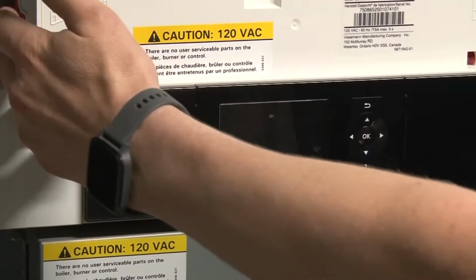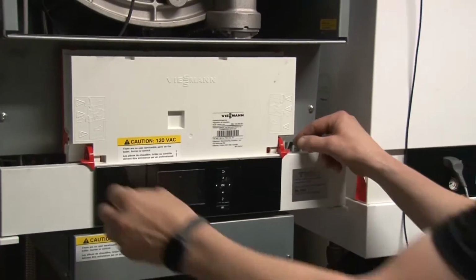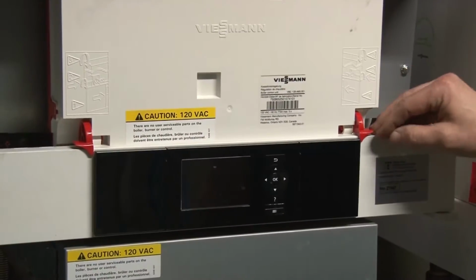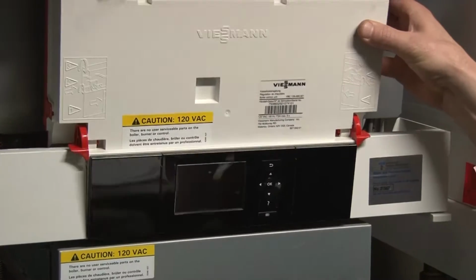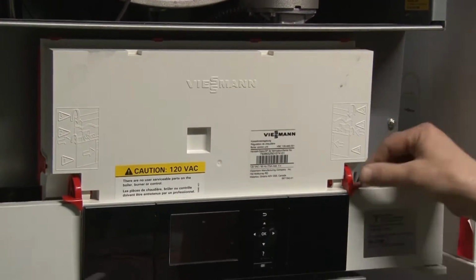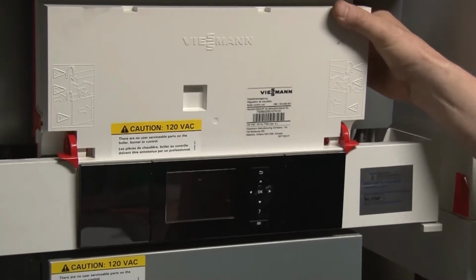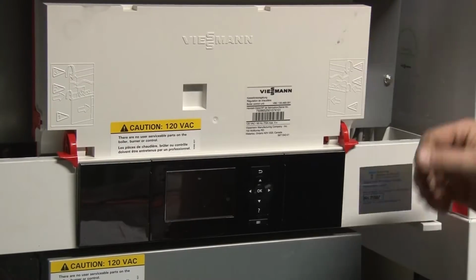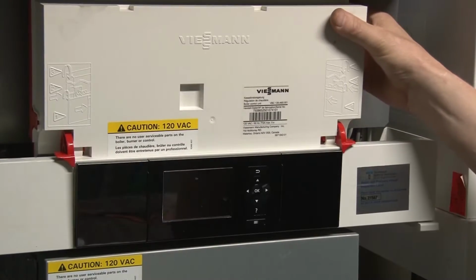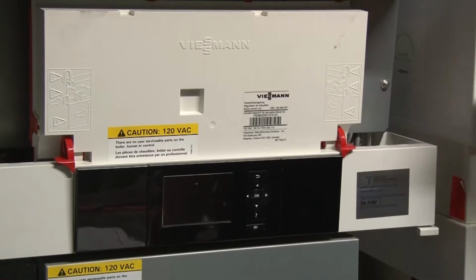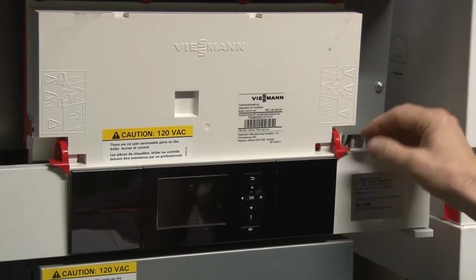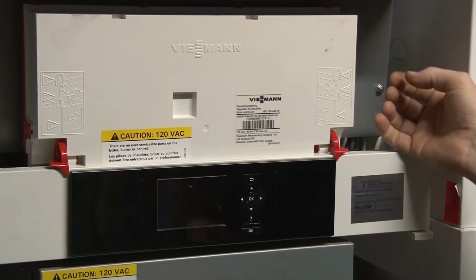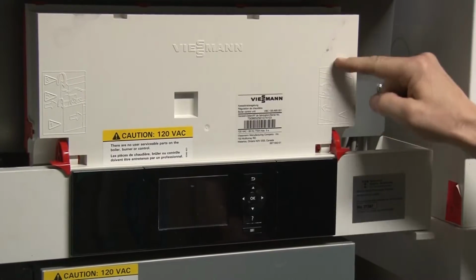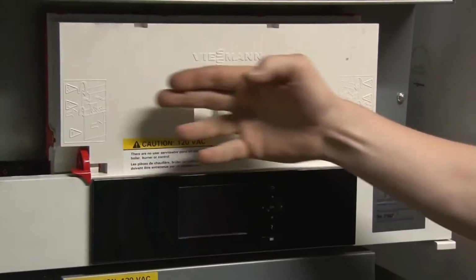We're gonna make sure those doors are closed. We make sure that these little clips are in the full down position. Otherwise, you're gonna have a little fight to get this control off. And in my experience, there's guys that are strong enough that they can force this control down. If I have my Wheaties in the morning, I might be strong enough to do that. And these little red clips will pop out and they'll go flying. So the idea there is to make sure they're in the complete reset position.